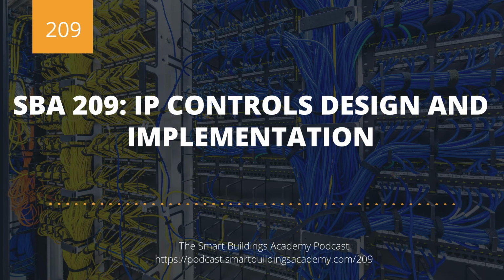With actual IP controls, you need to know not just their setup in the IP controller, but also what it is connecting to in the IDF, because you're no longer connecting to a supervisory device. You are now connecting to an IDF. You're connecting to a switch in the IDF or in the MDF. And the thing is, if you're connecting to a switch in the IDF or MDF, now you need to have a process that you've established with IT network admins around any updates, any upgrades that they do.